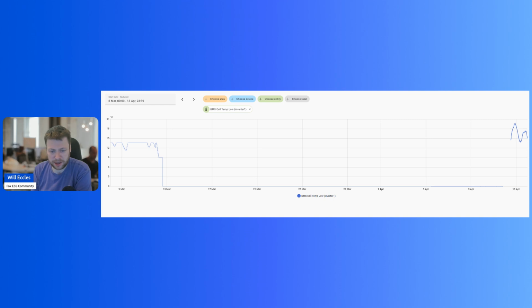I was looking at the BMS cell temperature low reading, which led me to think this wasn't actually a BMS temperature sensor, but a battery pack temperature sensor. It'd been offline for all this time. I'm not sure why, nearly 3-4 weeks later, it decided this was the time to cause the system to enter a standby fault mode. Towards the end you can see the temperature returned to normal, after I'd successfully resolved the fault.